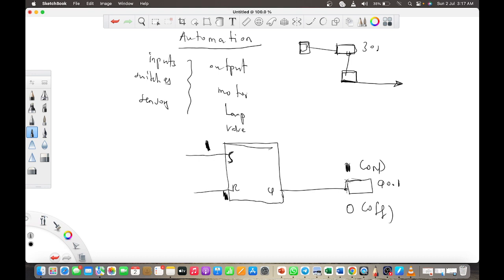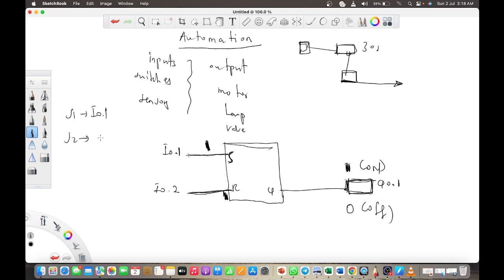I can regulate how the output goes on and off based on the input connected to the set and reset. For example, if this lamp comes on when switch I0.1 is pressed and goes off when I press I0.2 — a stop button — then when I press switch one, set becomes one and the lamp comes on. When I press the stop switch S2, the output goes off.